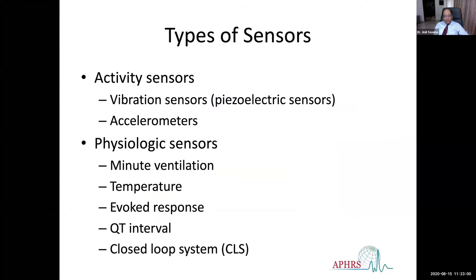So pacemakers have different kinds of sensors. There are activity sensors, still the most widely used, which could be vibration sensors, a piezoelectric crystal, or accelerometers, which sense acceleration. Then there are physiological sensors, which sense minute ventilation, temperature, evoked response, QT interval, or CLS.